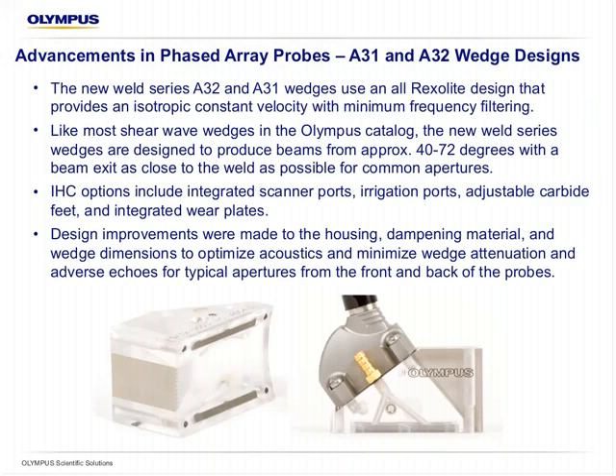So just as important as the new probes, and in some respects more important, are the design of the wedges that go with them. The new Weld Series A32 and A31 wedges use an all-Rexolite design that provides an isotropic constant velocity with minimum frequency filtering. That's the benefit of Rexolite and why most manufacturers use it. Like most shear wave wedges in the Olympus catalog, the new Weld Series wedges are designed to produce shear wave angle beams of approximately 40 to 72 degrees with a beam exit as close to the weld as possible for common apertures recommended in the aperture charts.